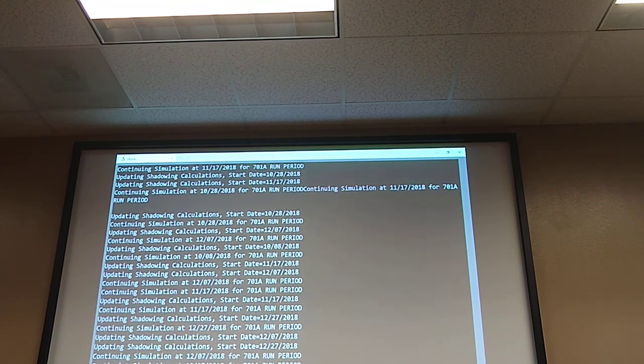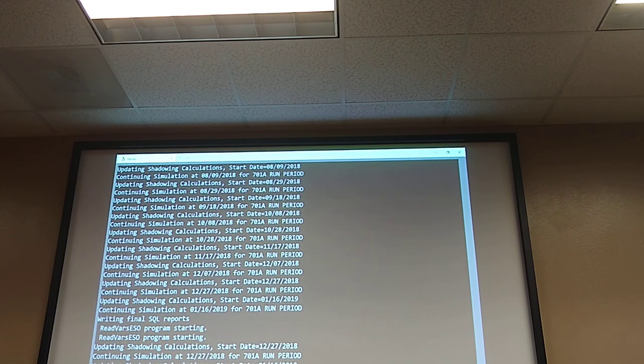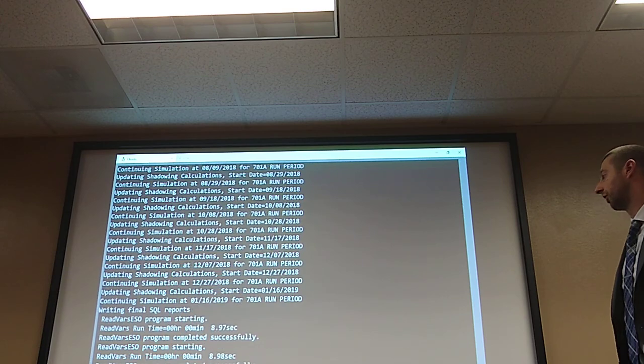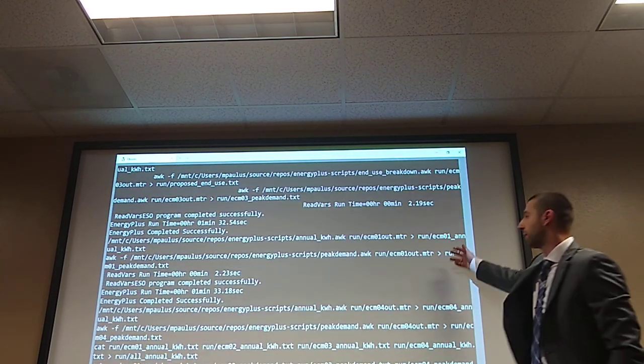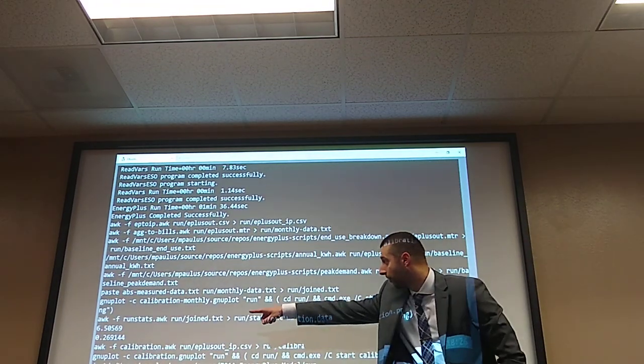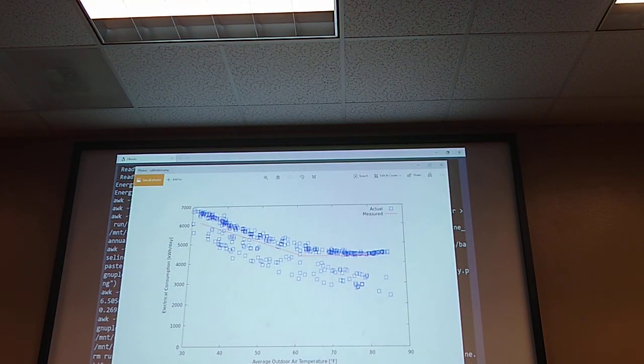The full pipeline took about two minutes to complete. The post-processing includes calculating peak demands, computing CV-RMSE metrics, and generating plots — all running in parallel. I also have it fill in a client-required spreadsheet template with calibration outputs automatically. EnergyPlus is slower than it needs to be — a single-duct VAV system requires around 20 EnergyPlus objects — but with this pipeline the whole workflow is automated, reproducible, and runs end-to-end with a single `make` command.